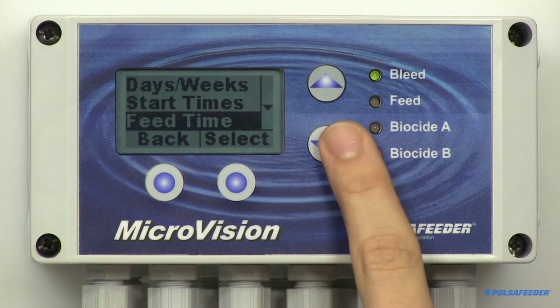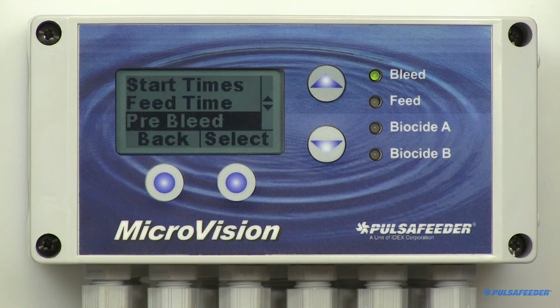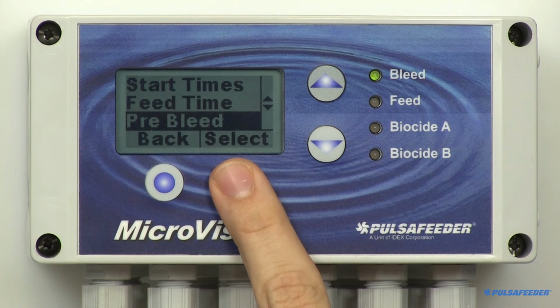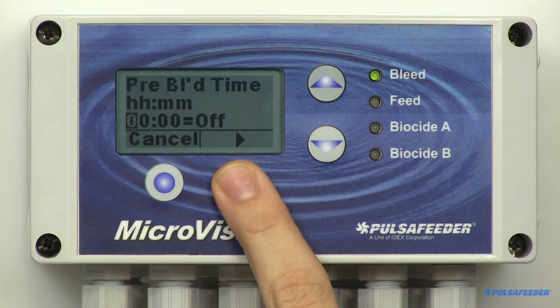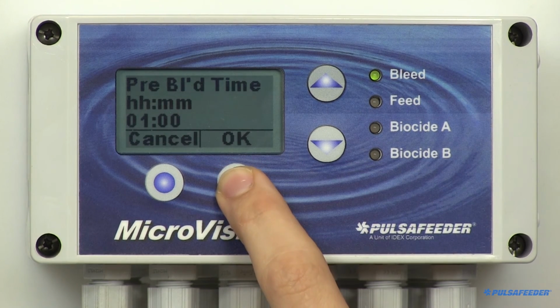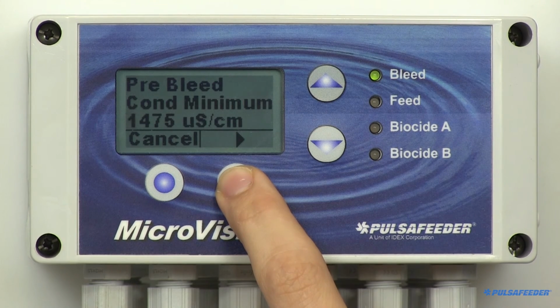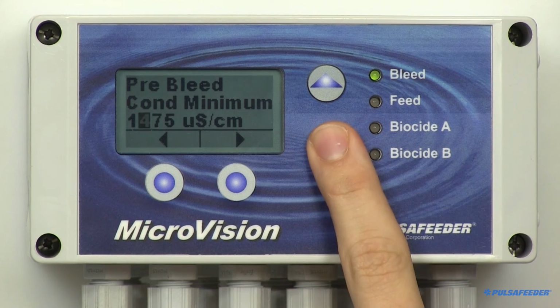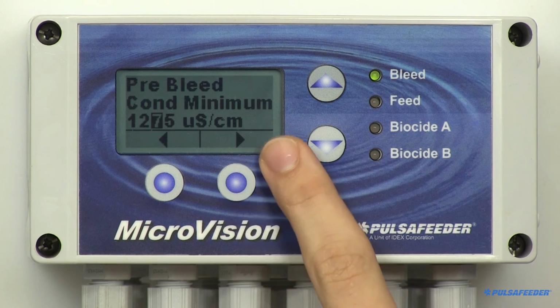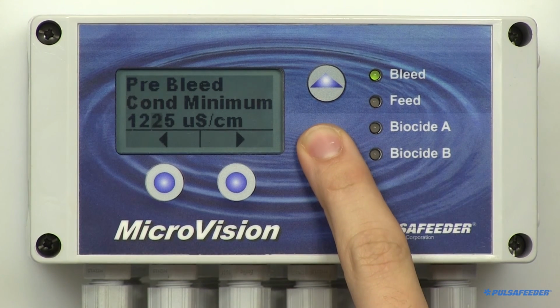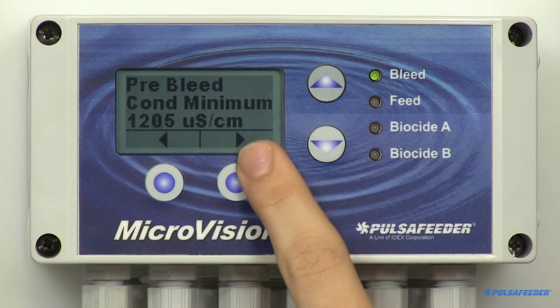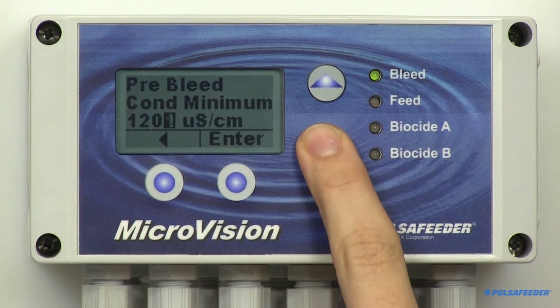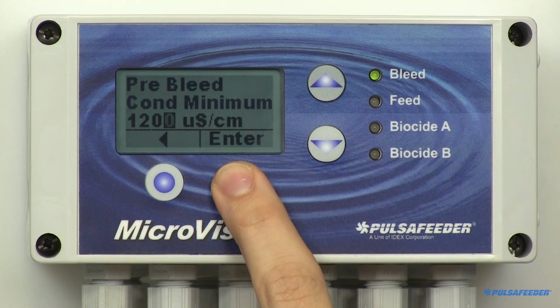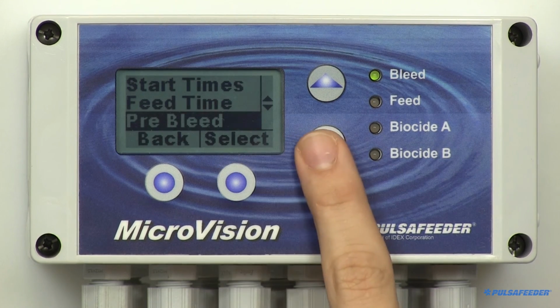The next option we'll cover is pre-bleed. There will be 2 settings, pre-bleed time and minimum conductivity value. From the biocide menu, highlight and select pre-bleed. Now enter the pre-bleed time in hours and minutes using the arrow buttons and then hit OK. Next, enter the conductivity minimum value you want your conductivity to reach before the bleed cycle finishes and biocide is fed. Do this by using arrow buttons. Press Enter and OK to return to the biocide menu.